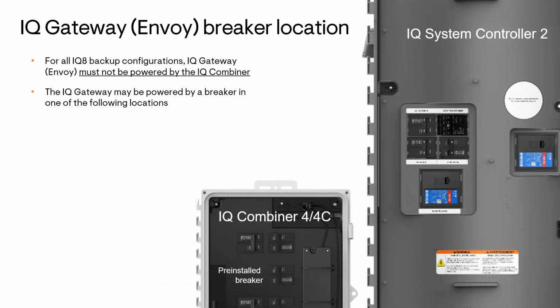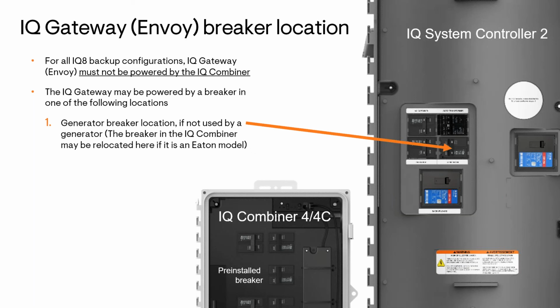All right, so for all backup power configurations, the IQ gateway, formerly called the Envoy, the breaker for the IQ gateway must not be installed in the combiner. Now, the reason is that the IQ combiner can at times be disconnected from the system controller by the relay, and this would obviously cause the Envoy to lose power. And we want the Envoy, or the gateway that is, to constantly have power as much as possible because, again, it's the communication device, it's the monitoring device. It allows us to change settings and behavior of the system. So we want it to be on as much as possible. So therefore, for all backup power configurations, the gateway breaker has to be located in one of the following locations. Could be in the generator breaker inside the system controller 2, if this slot is not being used for a generator.